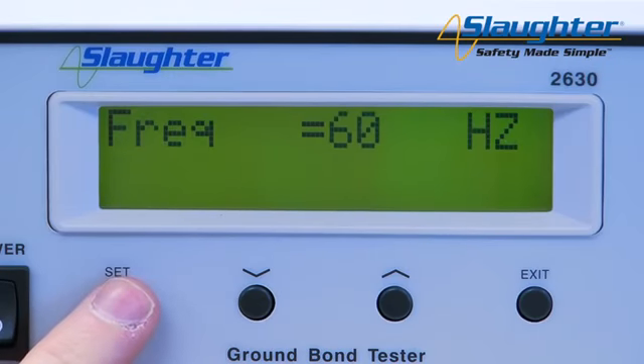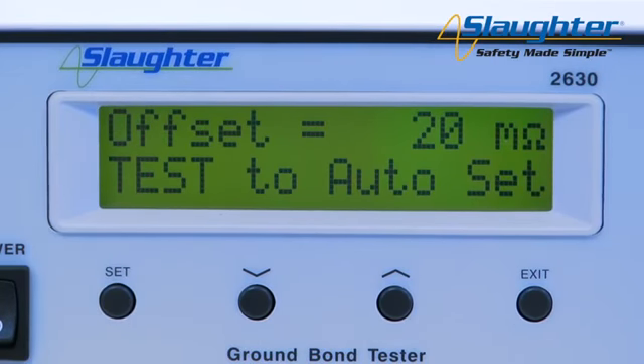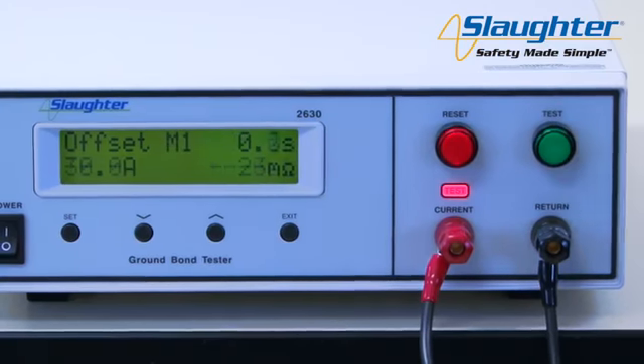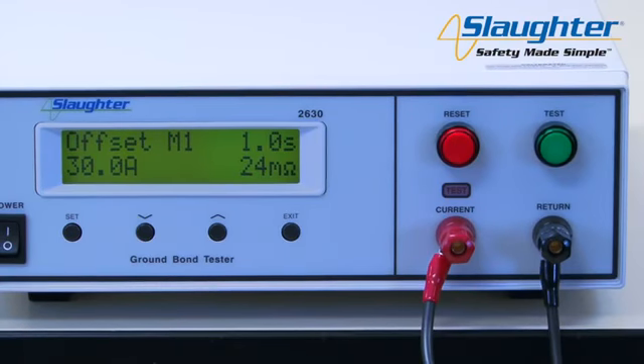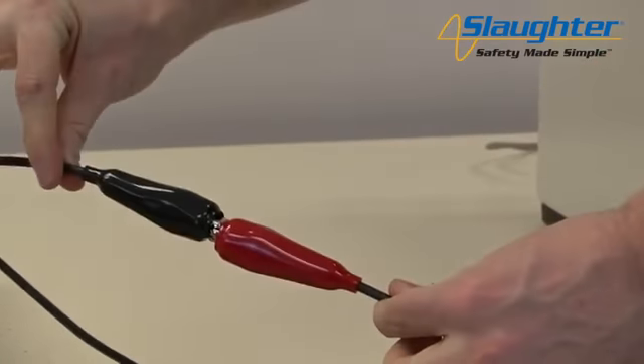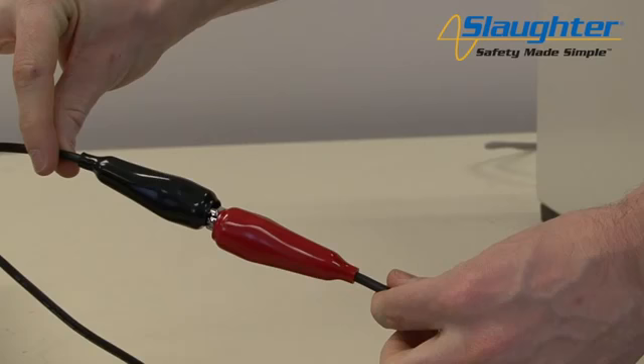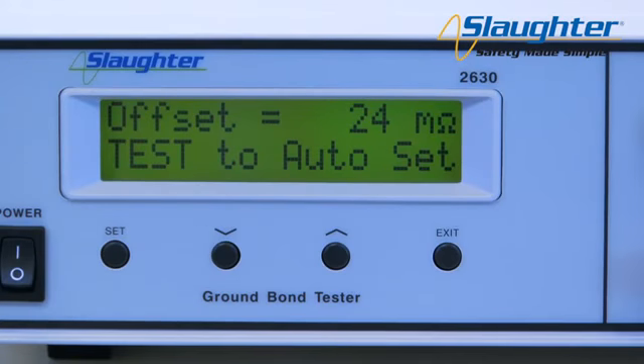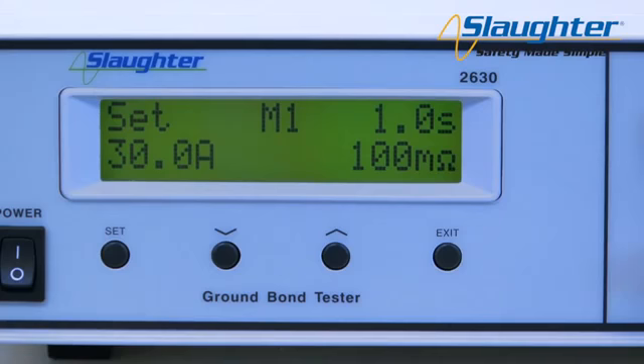Eventually, you will reach the offset parameter. The offset feature allows you to negate lead resistance from your ground bond reading. This is designed to help you avoid any false failures caused by your resistance value going above your resistance high limit. You can set the offset in 2 ways. You can manually change the numeric value by using the up and down arrow keys. You can set a maximum of 100 milliohm offset. You can also automatically set the offset value by simply pressing the test button. In order to automatically set the offset, make sure that the current and return leads are shorted together. This ensures that only the lead resistance will be subtracted from your reading. Once you are finished setting all test parameters, press the Exit key to return to the Perform Test screen.